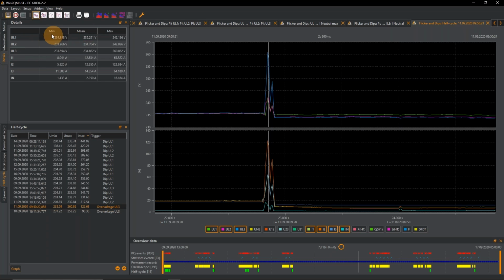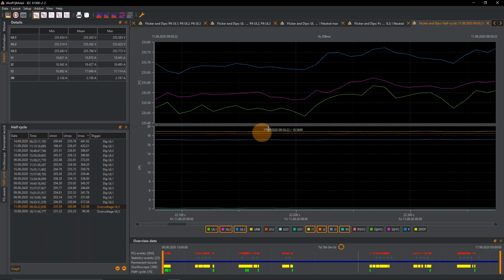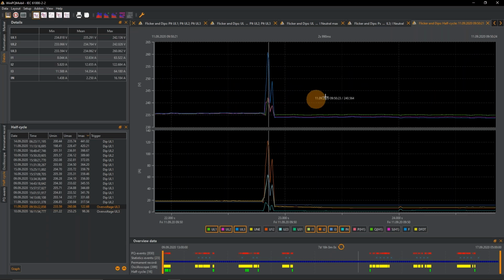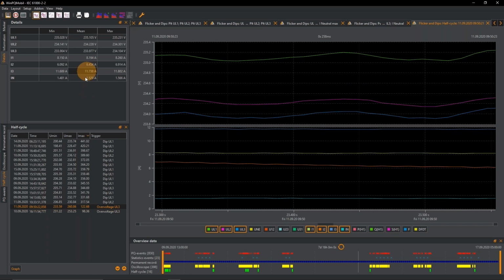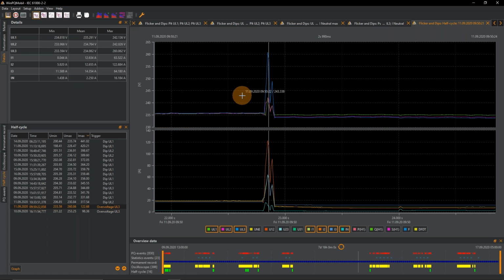If you click on the detail box, you see the minimum, mean, and maximum values of all the data that is displayed currently. So if I zoom in here, it will show you the mean value around 18 amps on phase 1, 2, and 3. So something was running, the machinery was running on there. If I zoom in on here, it was around 6, 1, and 11 amps. So this was obviously when the machine shut down. You only need this when the scaling is that high and you cannot see a difference between this line and this line at first sight. So this is a very convenient way, with this detail box, and here you see the maximum, minimum, and mean values. This could be very useful sometimes.